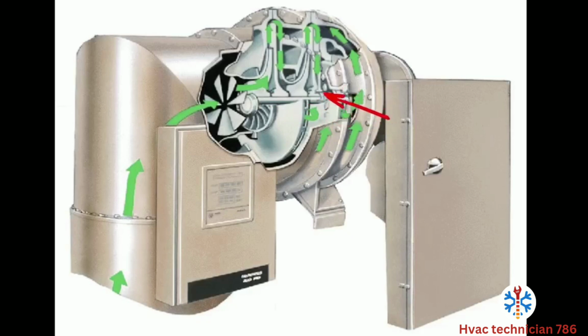The second guide vane is a variable guide vane. That is the armature that sticks out the side here that's controlled by the actuator. In a CVHE or G, the second impeller has a fixed guide vane, then it will flow through its impeller into its diffuser and into a variable guide vane for the third stage impeller before it cycles around and goes out the discharge.